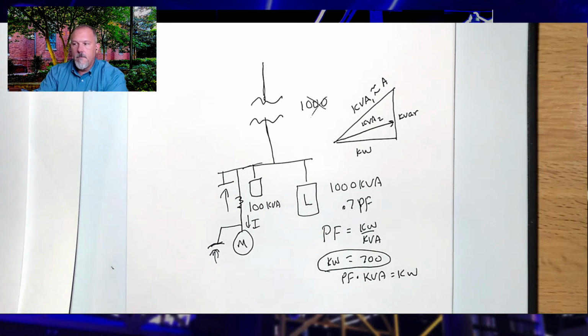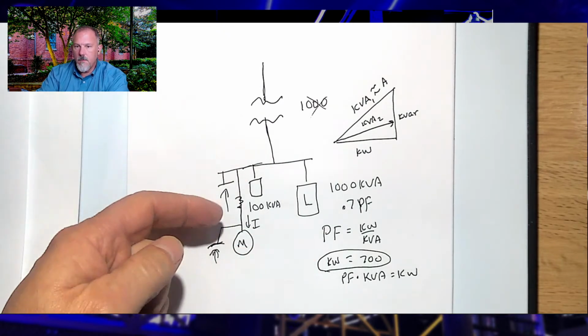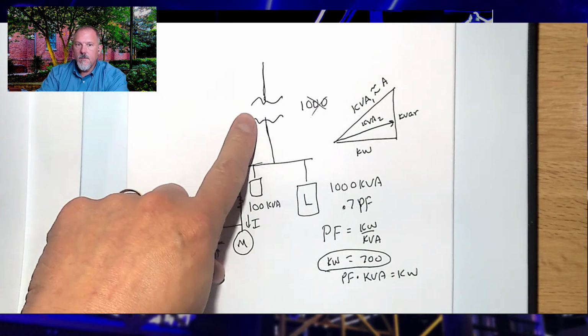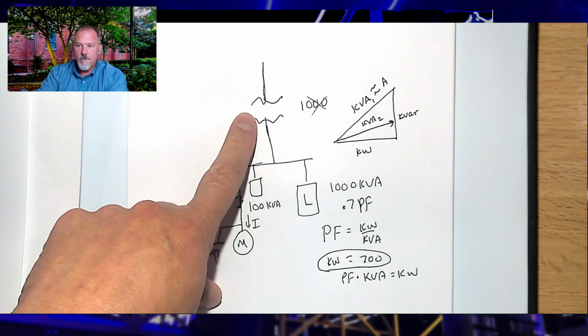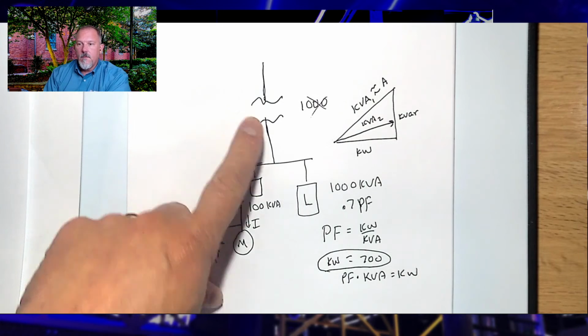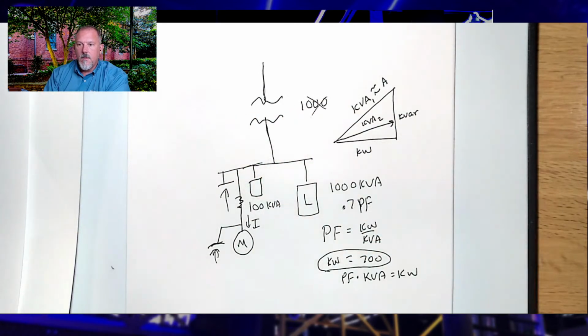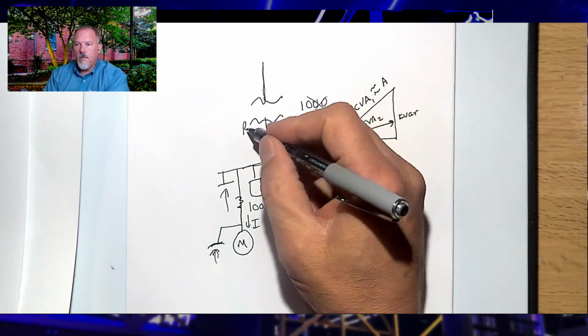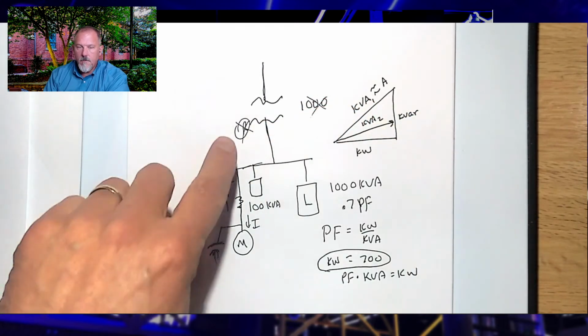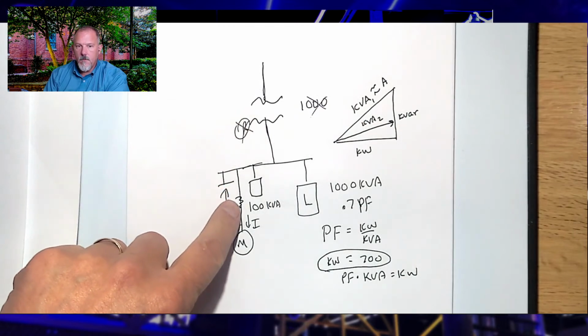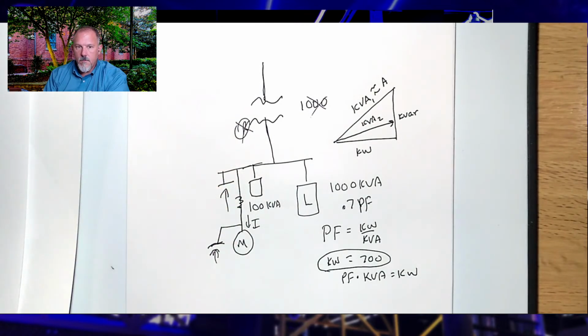You know where most of your impedance is? When we do fault studies, where do we count? We don't really even hardly pay attention to those lines. We pretty much look at the impedance of the transformer. Yeah. And the X over R ratio for a transformer is usually what, 10 to 1 or something like that. So it's a very highly inductive system, and the resistance of it is pretty small. So again, since there's not a lot of resistance here, and there's not a lot of resistance down here, the chance of saving real watts is not significant.